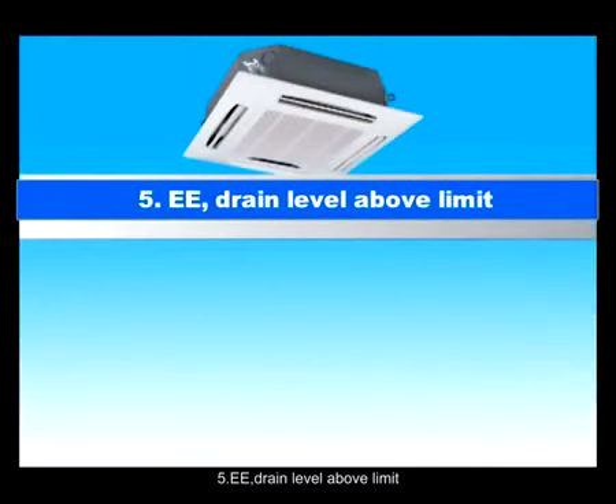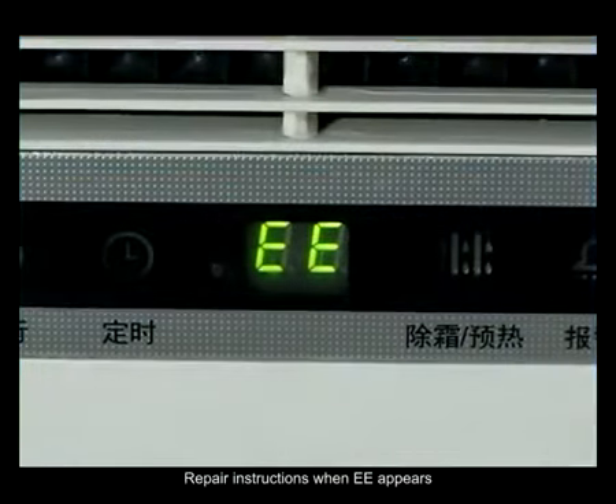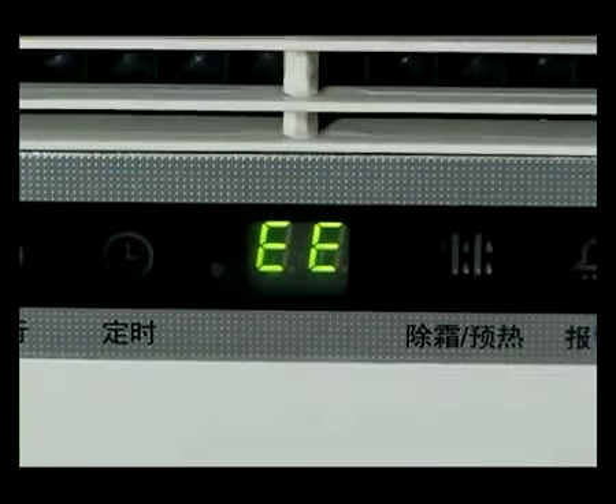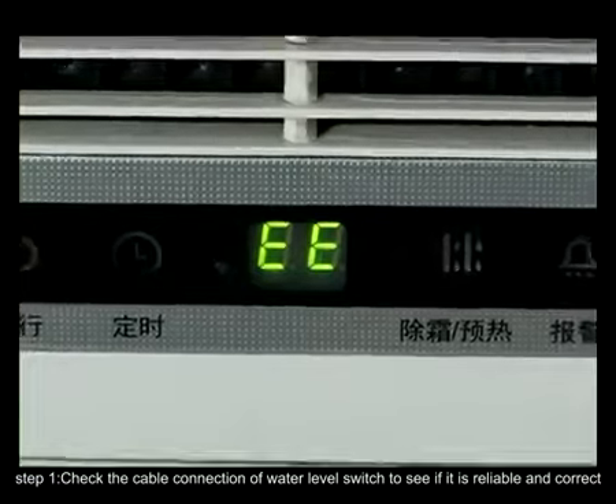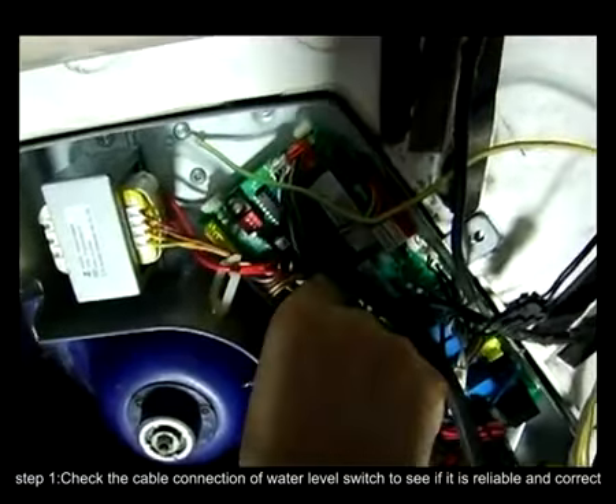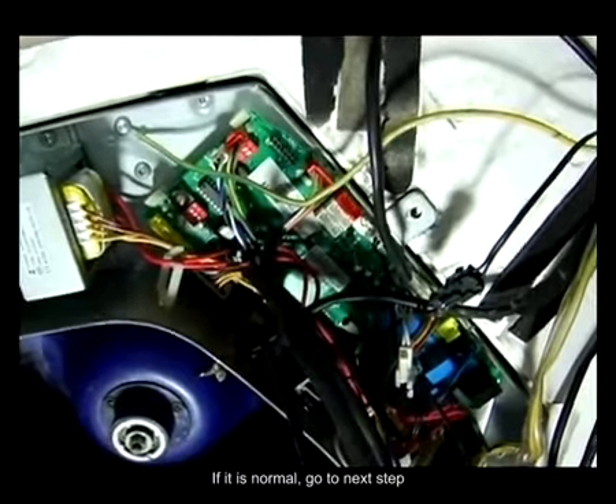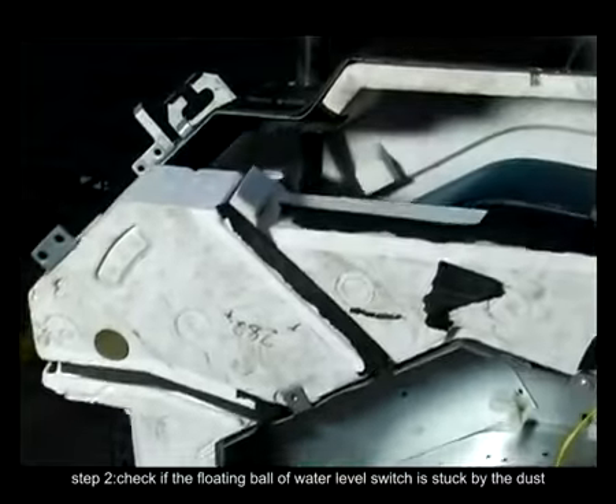5. EE, drain level above limit. Repair instructions when EE appears. Step 1. Check the cable connection of the water level switch to see if it is reliable and correct. If it is normal, go to the next step. Step 2.